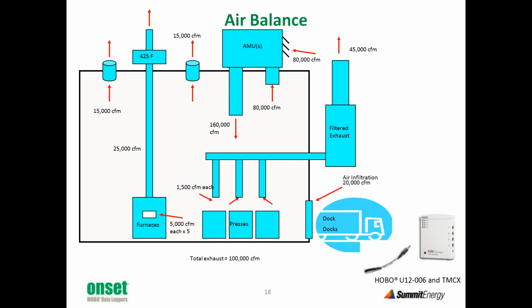This is an example air balance. If you have a factory, just draw a square and figure out what's coming in and what's going out. You may have exhaust hoods, you may have air makeup units. This is a way to get a feel for where the air is coming in and going out. So there's two important points here. The first is ventilate on demand. Only bring in the amount of outside air that you must to get the job done.